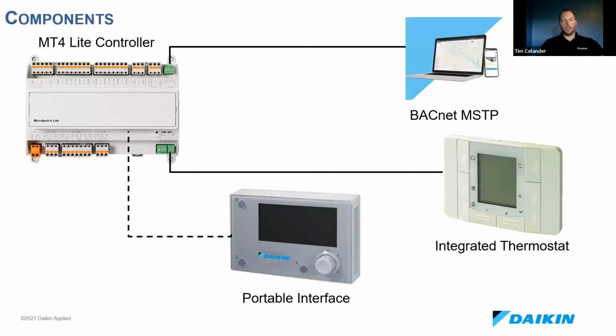So you can see here in the top left, we're looking at the PreciseLine controller. It's a defeatured MT4, which is the controller we're using in the new Rebel Applied product. It's going to come with a native BACnet MSTP option, so you can connect to a BAS if it's available in your market. If not, you're able to operate as a standalone controlled unit. The integrated thermostat on the bottom right is going to always come with the controller on the unit. That sits in the space. It allows some temporary set point adjustment.